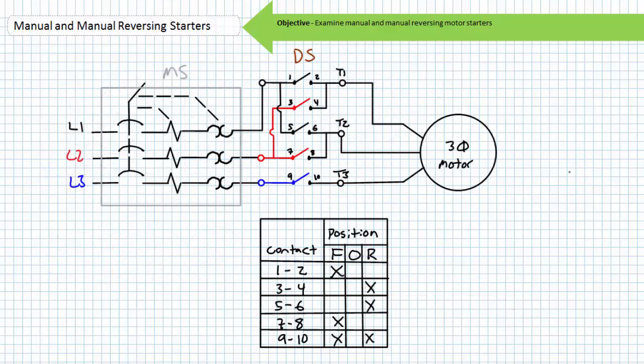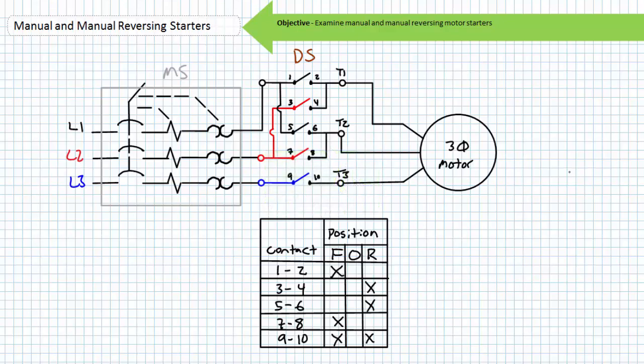Let's now discuss manual reversing motor starters. Recall from the rotating magnetic field lecture available at the Big Bad Tech channel that direction of the rotating magnetic field produced by a stator is dependent upon applied phase sequence. A manual motor starter will only allow an industrial three-phase AC motor to rotate in one direction only. For this reason, manual motor starters paired with a drum or rotary cam switch are found in applications necessitating bidirectional rotation.